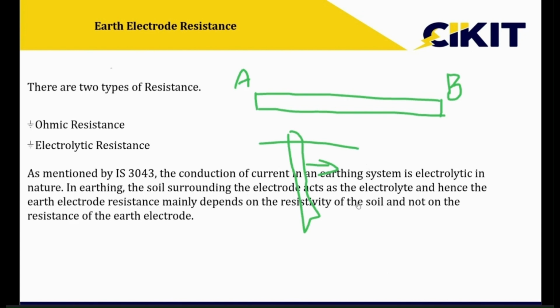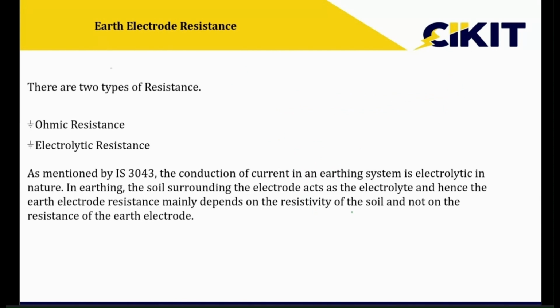The performance mainly depends upon the surrounding environment, and the standard highlights that the resistance associated with earthing is electrolytic in nature. So the resistance we discuss in earthing is not the same resistance we discuss for cables. When we buy a cable from the market, the data sheet mentions the resistance per meter length of the conductor, but that is ohmic resistance. In earthing, we are discussing electrolytic resistance. Both are different. The earth resistance is electrolytic in nature, and it mainly depends upon the soil in the surrounding environment, and not on the material which we are using.